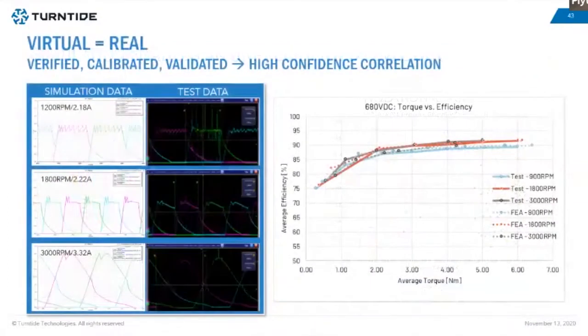It's very important to verify, calibrate, and validate simulation models so that what the models are predicting is correct, real, and accurate. On the left side, you can see comparison between simulated current waveforms and actual waveforms on the scope. On the right side, comparison between test data and FEA data from 900 RPM to 3000 RPM, going from 10% torque to 100% torque. Our predictions are within 1%.